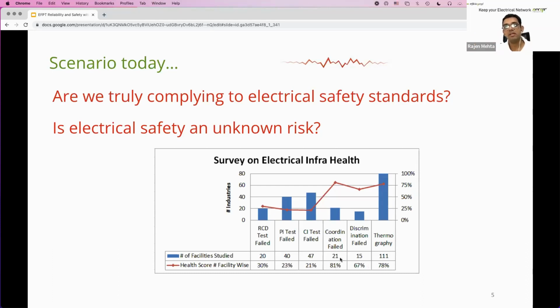Coordination and discrimination: we found that almost 60 to 80% of facilities have miscoordination between the HT all the way to the LT, to the load end of various breakers, relays and so on. And thermal imaging, although a lot of industries have started doing it, we found in 111 facilities, 78% of them had hotspots of varying degrees, based on standards like NFPA and IS 16168 for thermography.